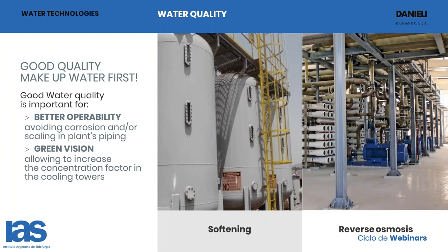Coming back to makeup water: it is very useful to have good quality makeup water. You typically use a softener to remove hardness — specifically calcium and magnesium — to avoid scaling problems inside the cooling circuit. Or you can use reverse osmosis systems to remove other salts as well, not just the cations calcium and magnesium, but also anions such as sulfates or chlorides. When you look for a makeup water system, you must know what you need to remove from the water.